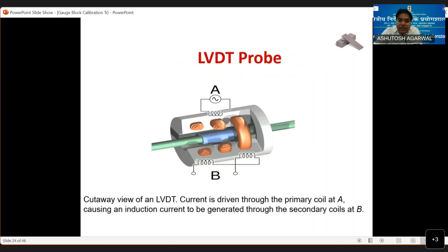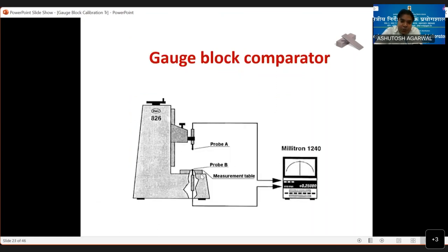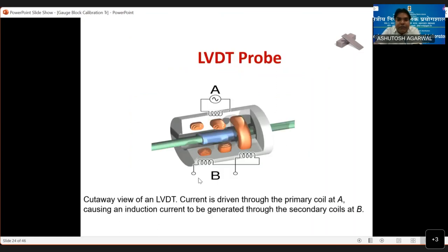And then how does it work? These two probes, A and B, they call them LVDT probes. They work on induction current. Current is driven through the primary coil, probe A, causing an induction current in the secondary coil. So basically, a voltage is generated when the two probes touch. A voltage is generated, and that voltage is calibrated in terms of length.